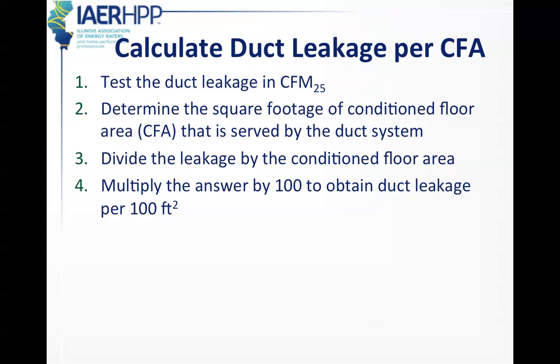Because the code is written in duct leakage per conditioned floor area, that's per 100 square feet of floor area, we're going to teach you how to do this right now. First you would test the duct leakage. You're going to determine the square footage of conditioned floor area, CFA, that is served by this duct system that you just tested. It's not the whole floor area of the house. You divide that leakage by the conditioned floor area that is served, and then you multiply the answer by 100 to obtain the duct leakage per 100 square feet. The example would be, when we run the duct testing fan, it tells us that our leakage for this duct system is 118 CFM at 25 Pascals. The system serves 2,300 square feet of this home. We simply take 118 divided by 2,300 and multiply that number by 100. And we would get 5.1 CFM per 100 square feet.